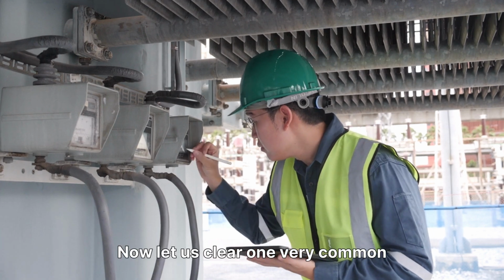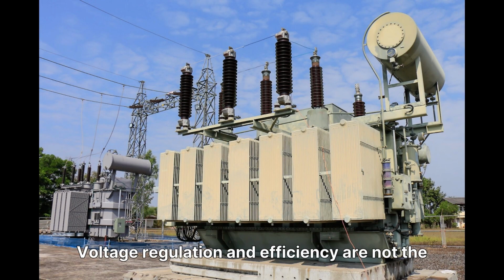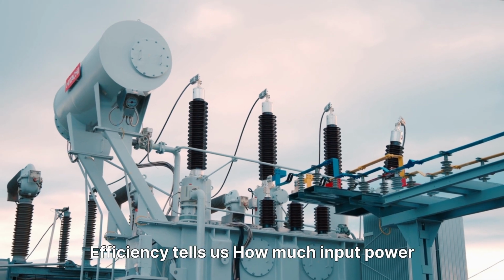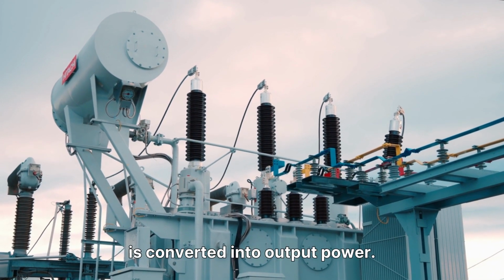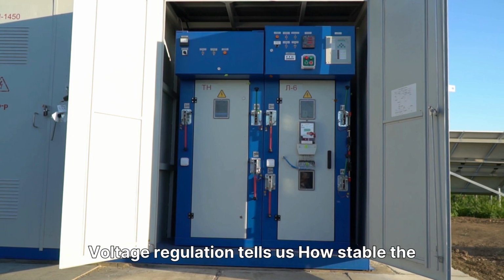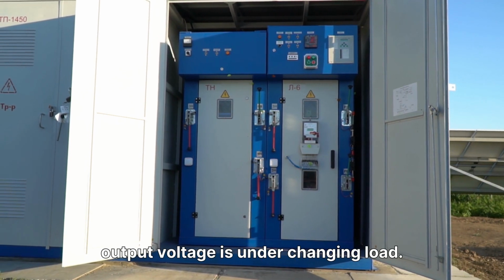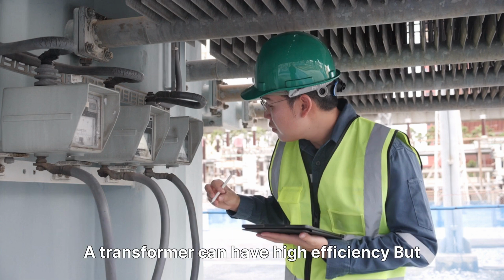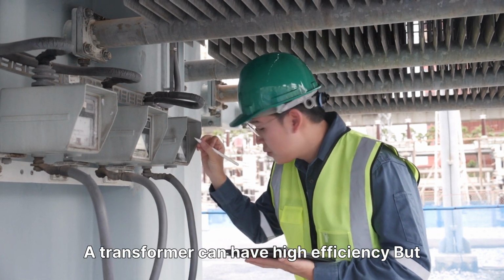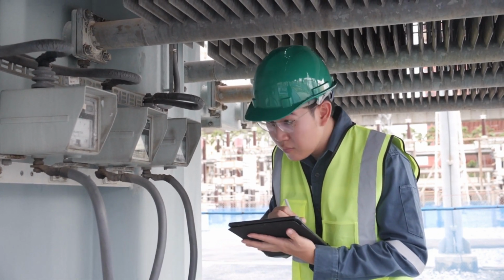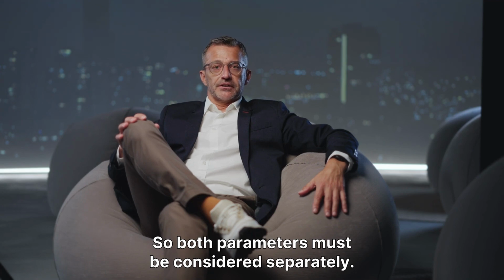Now let us clear one very common confusion. Voltage regulation and efficiency are not the same. Efficiency tells us how much input power is converted into output power. Voltage regulation tells us how stable the output voltage is under changing load. A transformer can have high efficiency but still have poor voltage regulation. So both parameters must be considered separately.